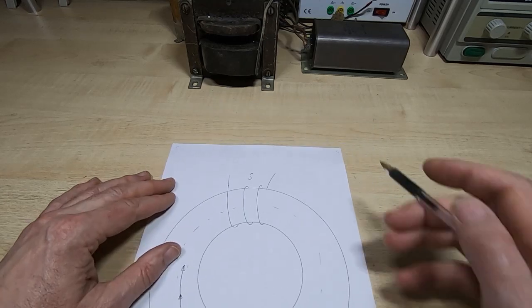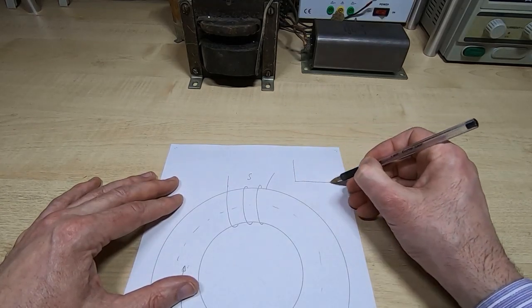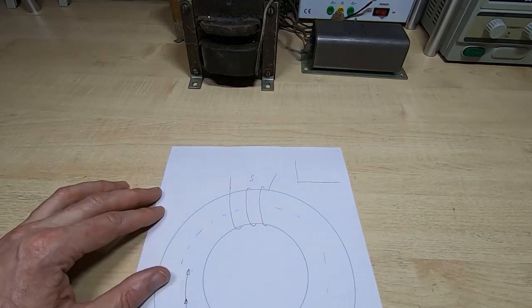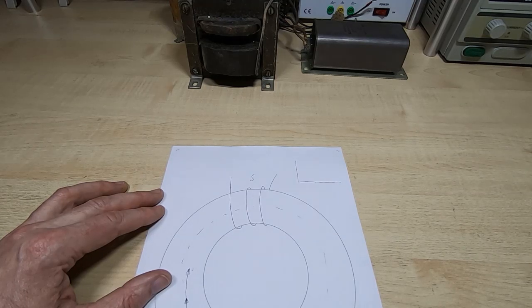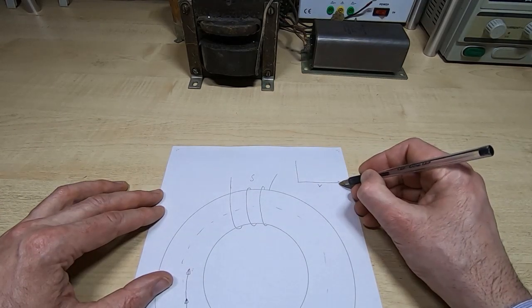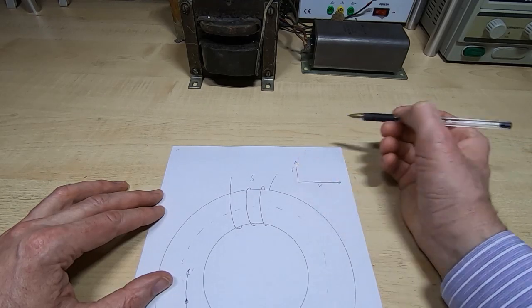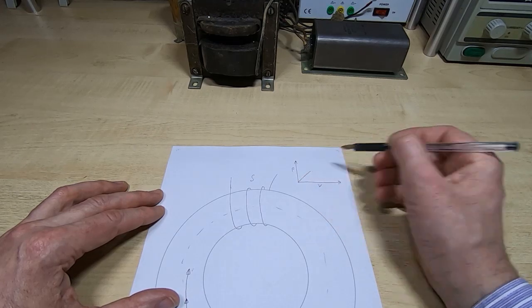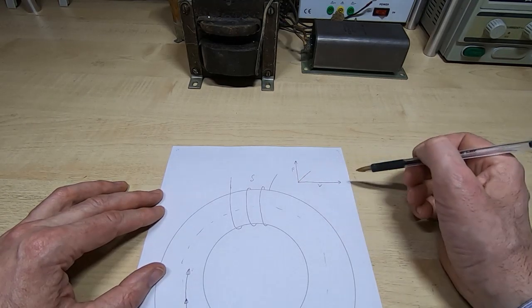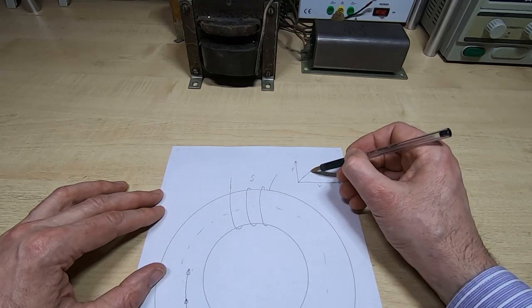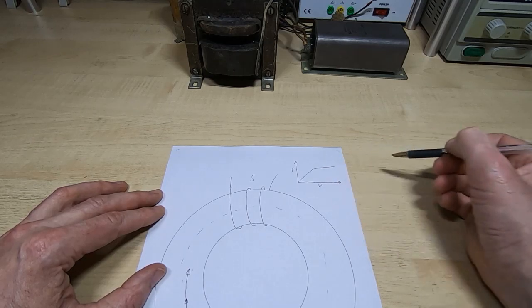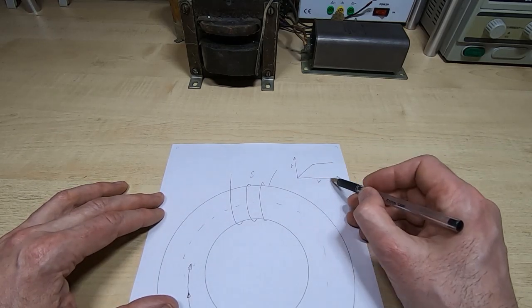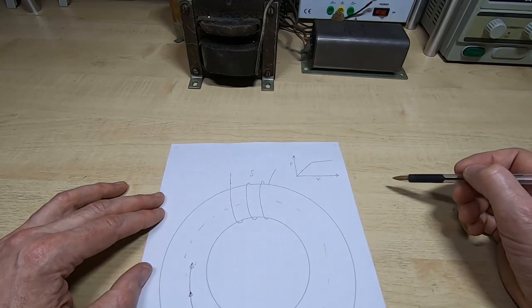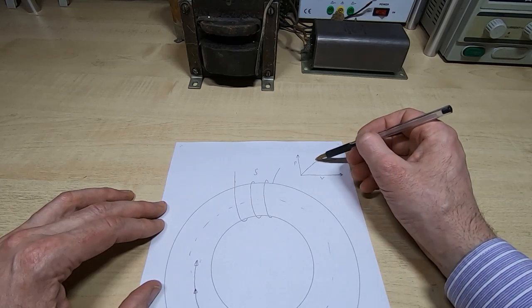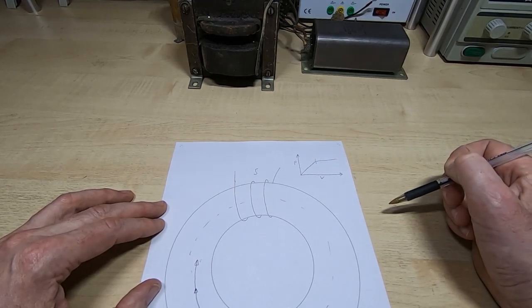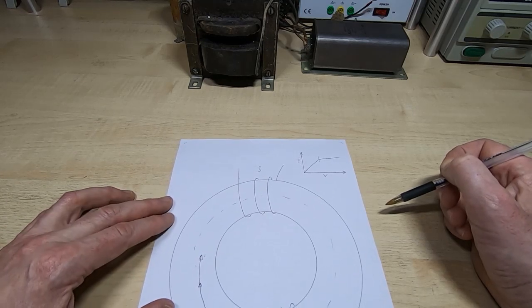So if we look at that in terms of a graph, then we have the voltage increasing and the flux increasing. So if we say the X scale is the voltage and the Y scale is the flux, they will start off in a fairly linear fashion. So as the voltage increases, the flux will increase, but beyond a certain point we'll reach what's called the knee, and the flux increase will drastically level out. So even though you'll carry on increasing the voltage, the flux cannot go any higher. And normally in a standard transformer you must avoid going into this region of the curve, otherwise the transformer will overheat and probably burn out.